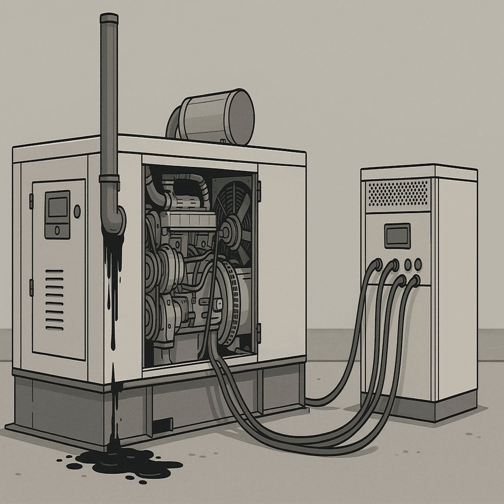So how often should you do this and how hard do you need to push it? Well, recommendations vary slightly, but a common guideline for many manufacturers is to perform a load bank test monthly. Monthly, okay. Yeah, for at least 30 minutes, and the load should be at least 30% of the generator's rated capacity. Some sources are actually more aggressive, suggesting you really need to hit 75% or even more of the maximum load to get things truly hot enough. So somewhere between 30 and 75% consistently. Ideally, operating regularly between, say, 40% and 75% of the maximum rated load is a great zone for keeping things healthy during normal use or testing. The key is avoiding those prolonged periods of very low load.